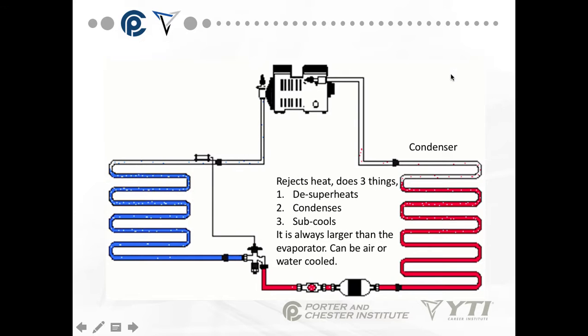De-superheating is taking the heat coming out of the inside of the building, plus the heat generated by the compressor, and lowering it to the temperature where the refrigerant can condense — a change of state from vapor to liquid. Once condensation occurs, the refrigerant further drops in temperature, which is called sub-cooling. The condenser in an air conditioning system is always larger than the evaporator. It can be air or water-cooled, but most you'll see are air-cooled.